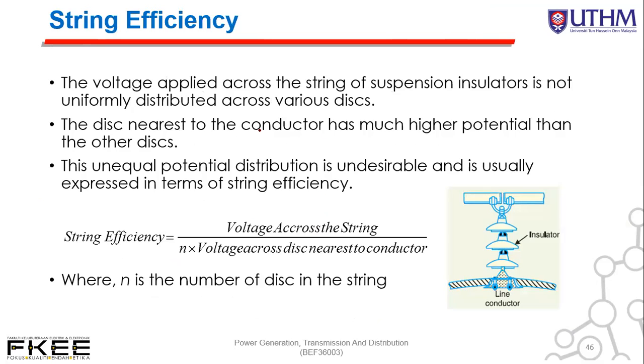Kemudian kita akan belajar sikit tentang string efficiency. Okay, the voltage applied across the string of suspension insulator is not uniformly distributed across various discs. So, the disc nearest to the conductor has much higher potential than the other discs. This unequal potential distribution is undesirable and is usually expressed in terms of string efficiency. So, formulanya adalah string efficiency equal to voltage across the string divided by N times the voltage across the disc nearest to the conductor, yang bawah ni. Voltage across the string ialah keseluruhan ni. N is the number of discs. Berapa banyak disc bergantung kepada jumlah N tersebut.